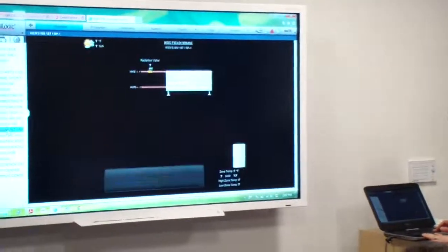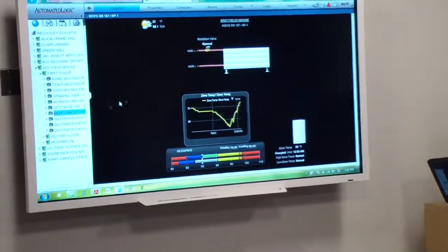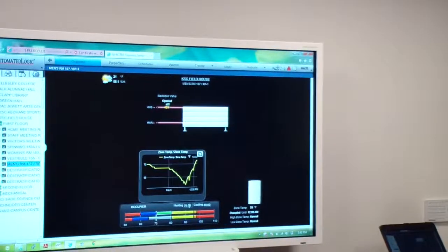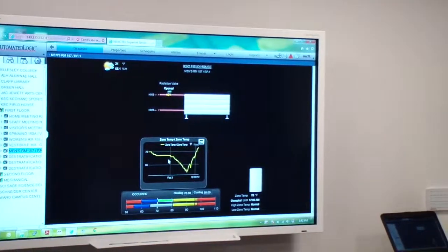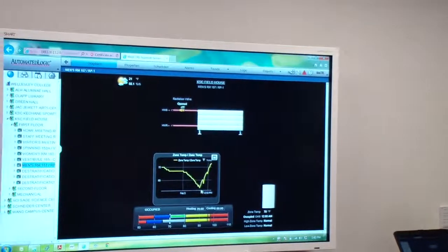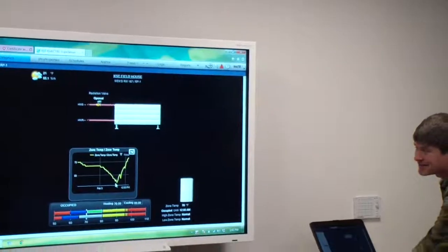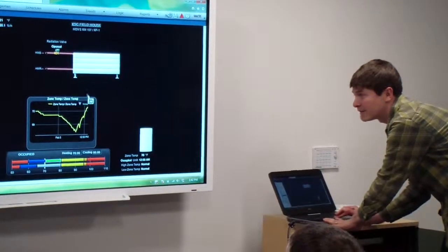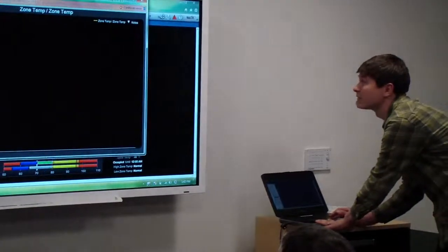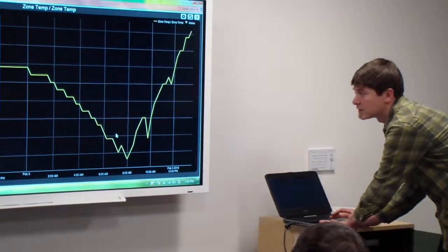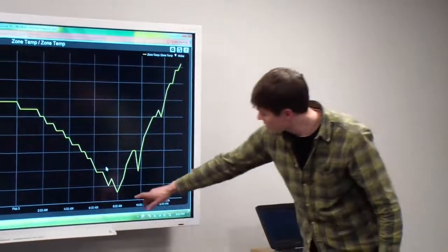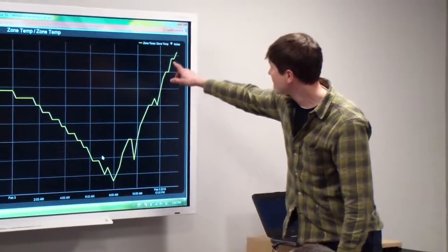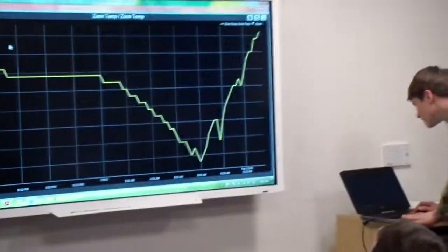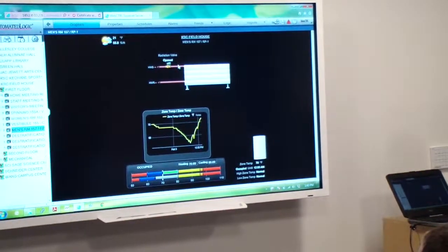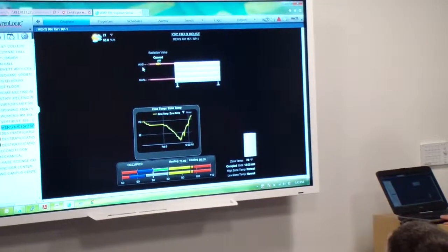Go back to the graphics for a moment. Switch over to the men's room. We can see there's a piece of radiant in there, heating at 70, cooling at 80. Looks like there was a little bit of a drop around here, so it's probably 68 and a half. If you guys want, you can actually expand the graph and get a clearer picture of what's going on. So you see that it dropped to about 68 and a half and has been coming up since, which is why we would see that the radiant valve here is open.